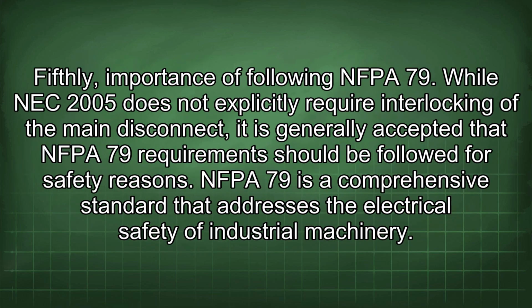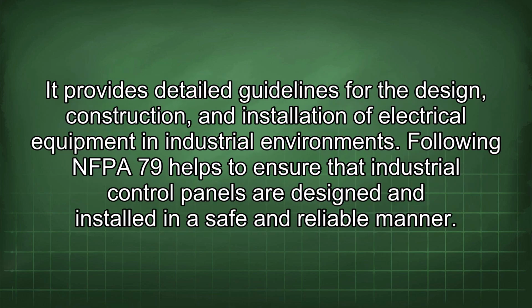Fifthly, importance of following NFPA 79. While NEC 2005 does not explicitly require interlocking of the main disconnect, it is generally accepted that NFPA 79 requirements should be followed for safety reasons. NFPA 79 is a comprehensive standard that addresses the electrical safety of industrial machinery. It provides detailed guidelines for the design, construction, and installation of electrical equipment in industrial environments. Following NFPA 79 helps to ensure that industrial control panels are designed and installed in a safe and reliable manner.